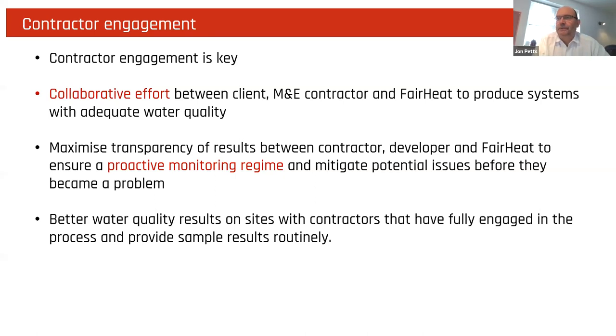The water quality does have a drastic effect on the efficiency of the systems, as Peter mentioned. We could get clogged valves, clogged HIUs, and it does increase wear on pumps and other moving parts within the system. And if it goes drastically wrong, then the pipework can deteriorate very quickly. Particularly, a word of warning to anybody out there that's got any carbon pipework installed: it's a nice, cheap, lightweight option, easy to install, but you have to get the water treatment spot on with that, because within very short periods the welds can be attacked and the bacteria can affect the pipework and it can pinhole very, very quickly.